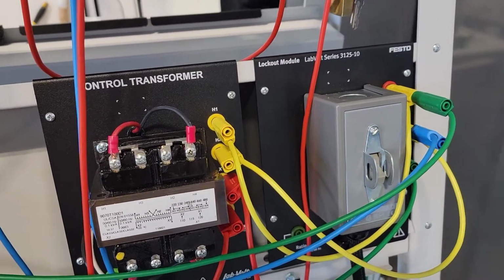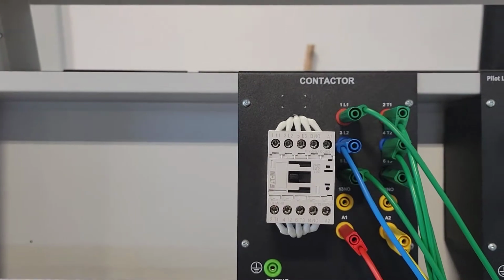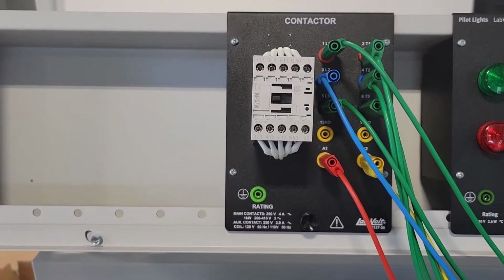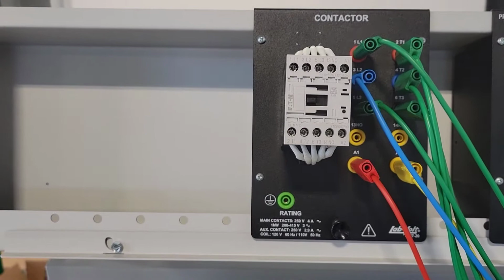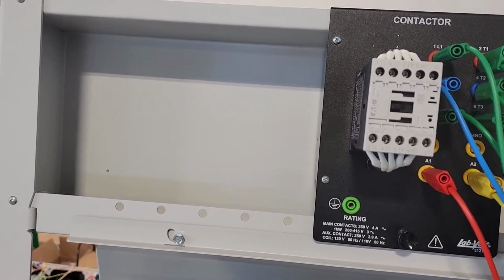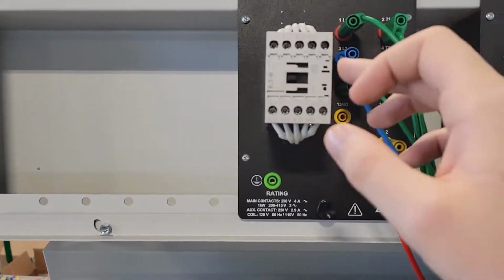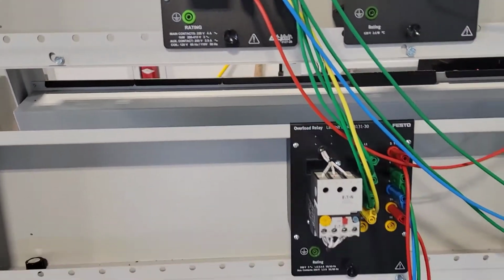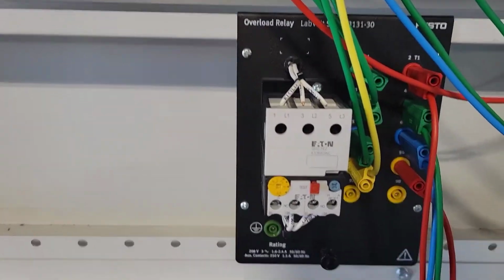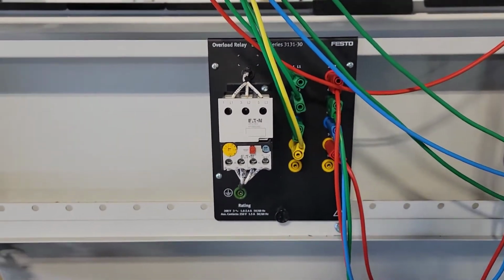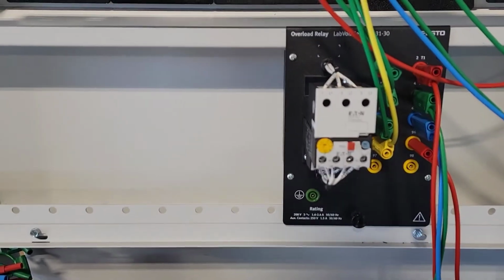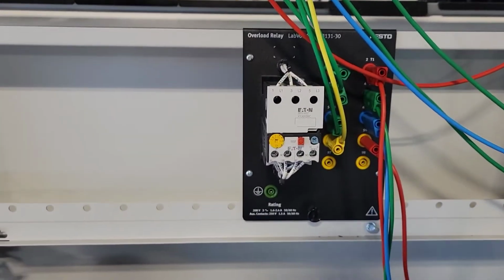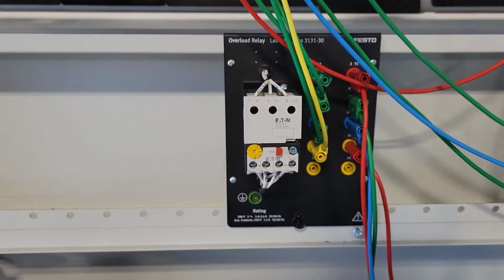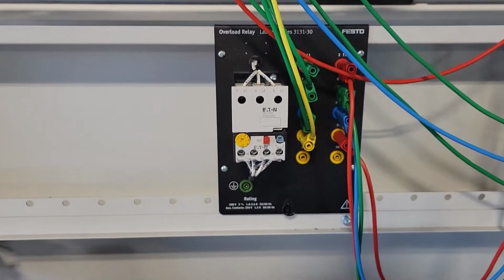And so on the high voltage side, from the lockout module to the contactor, this contactor will act as a control. The low voltage will control the high voltage side via a magnet on the inside. And then it'll come to this relay, and this relay is for a safety precaution, so that when the motor starts to heat up, there's a temperature sensitive coil in there, and once it reaches a certain temperature, it flips.